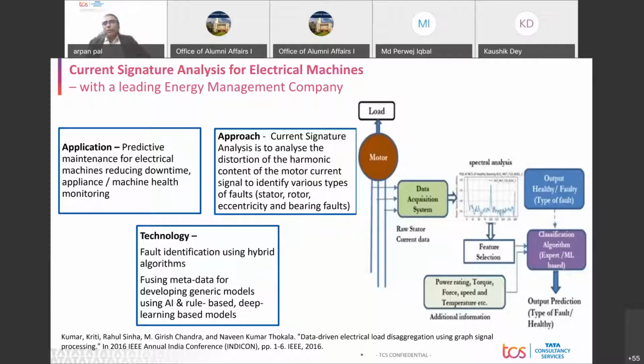What we do here, without going into too much detail, is current signature analysis to analyze the harmonic distortion of the motor current signal to identify various types of faults, like stator fault, rotor fault, bearing faults. All these have their own physics-based manifestation in the current, and we try to identify that. Then we use an AI/ML pipeline to extract features and do fault identification.